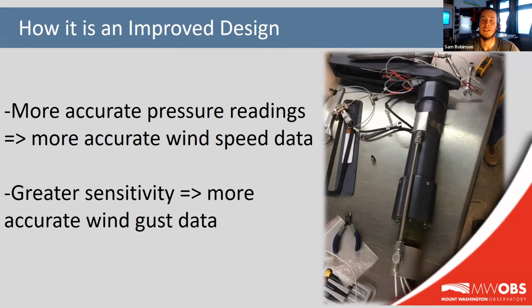This helps us in a few different ways, and it actually helps take care of our two main areas for improvement, which is the tubing length and ease of removal and installation. With a self-contained pressure system, we're keeping that total system volume much, much lower, which in turn helps keep that pressure dampening I previously touched on to an absolute minimum. With everything being self-contained in the body of the anemometer, we are also effectively eliminating any temperature changes like the long tubing length of Pitot 19 was subjected to. So these specific improvements do lead to more accurate pressure readings, which then equals more accurate wind speed data. Along with that improved accuracy, we achieved greater sensitivity to wind speed fluctuations, which also equals more accurate wind gust data.